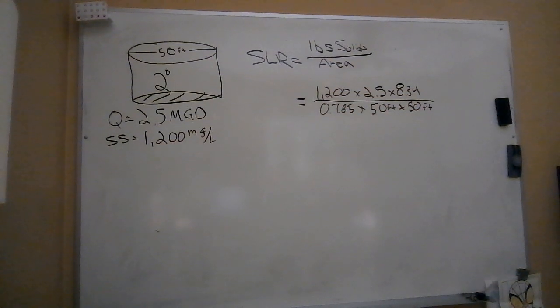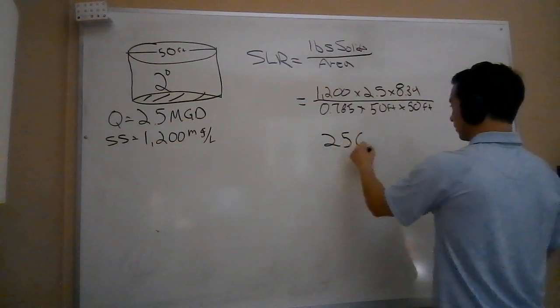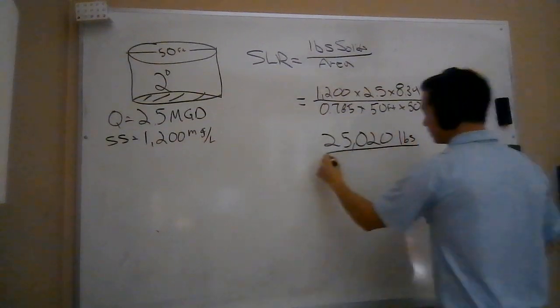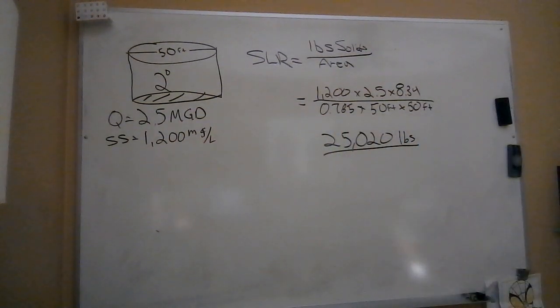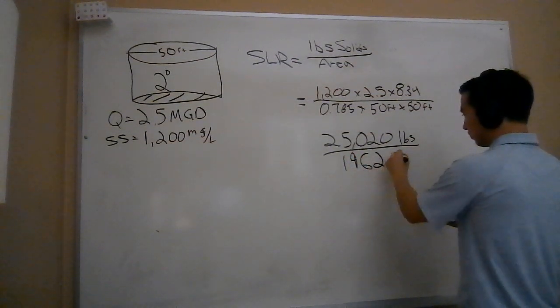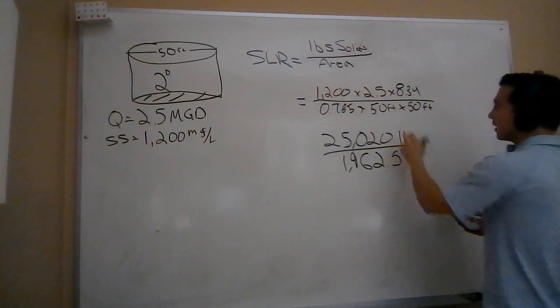When we run the top, we get 1200 times 2.5 times my 8.34 weight of water, and I get 25,000 pounds of solids. Divided by my area, so 0.785 times 50 times 50, that gets me to...